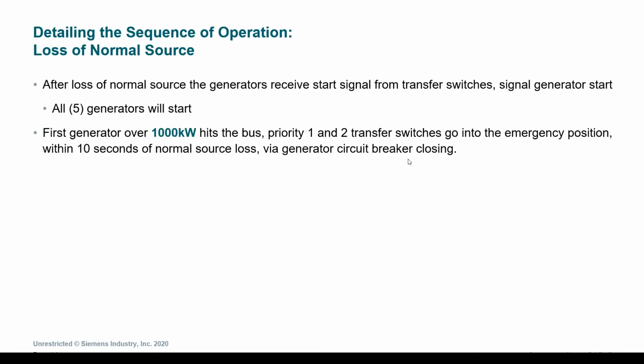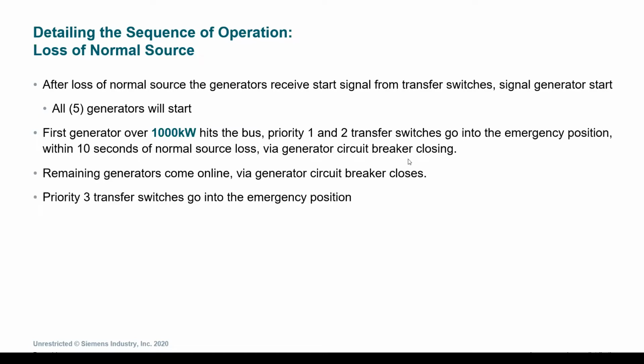We want to make sure, although the 500 kW engine generators may start quicker, that we have the first generator over 1000 kW carry that load. And this will allow the system to do it within 10 seconds of that normal source being lost. At that time, that first generator coming online, from there, the remaining generators come online and the associated generator circuit breakers close.